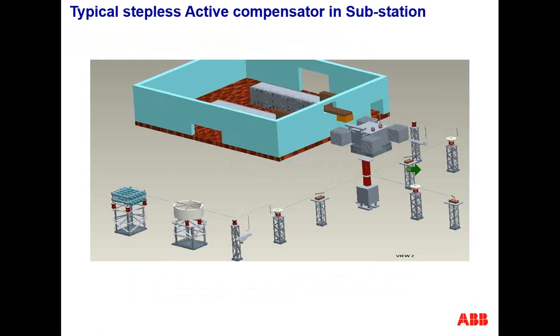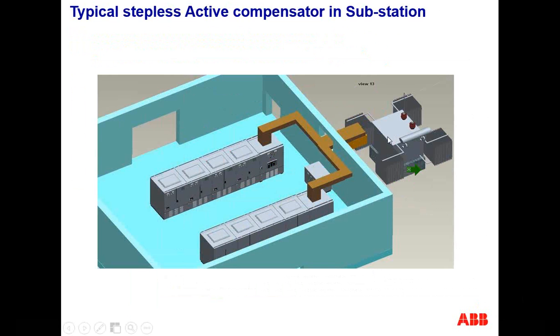Here is a typical installation photograph where we can have a filter reactor, as I said, which can take care of the part of the existing capacitor bank or the filter bank or the fixed compensation, and balance dynamic. We can add this module depending on the voltage level and ratio. So we can put the active compensator, which will take care of the rest of the power quality requirement.